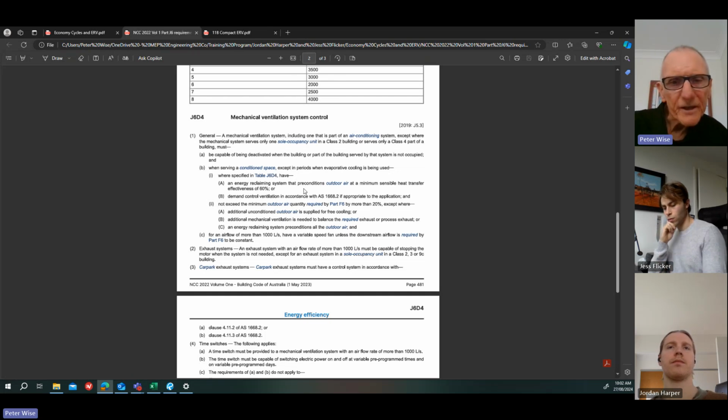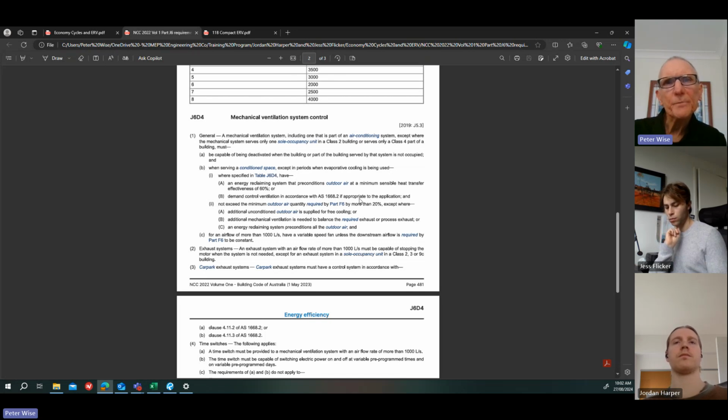They can tell you exactly what the efficiency of these units is. Now, A is ERV or demand control ventilation in accordance with AS 1668 Part 2, if appropriate to the application. And then there's a couple of things to bear in mind.